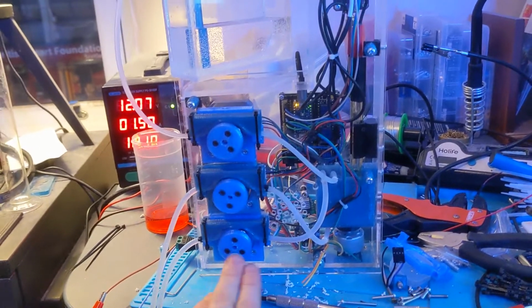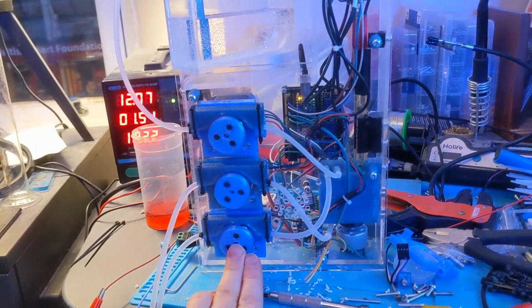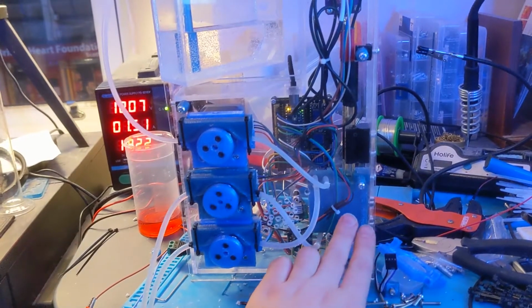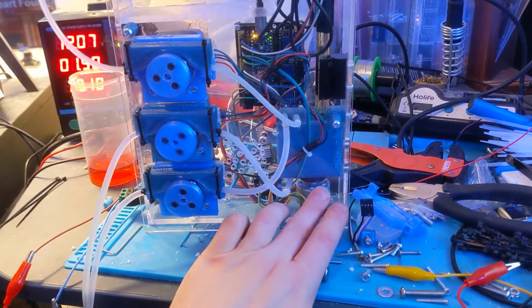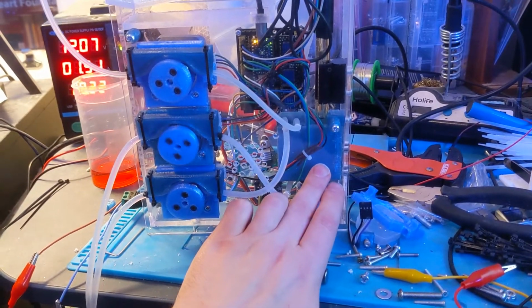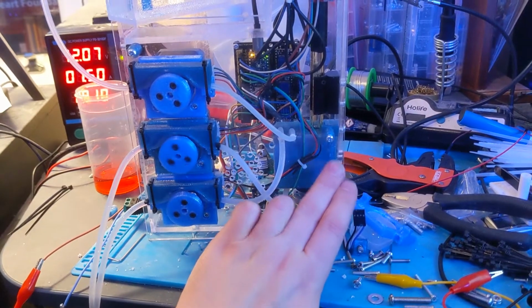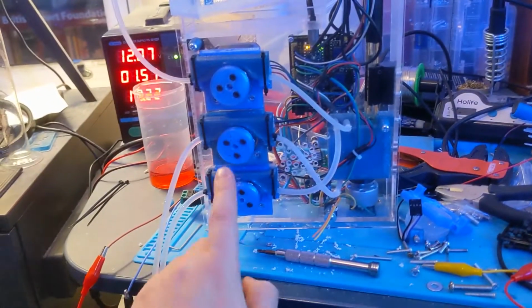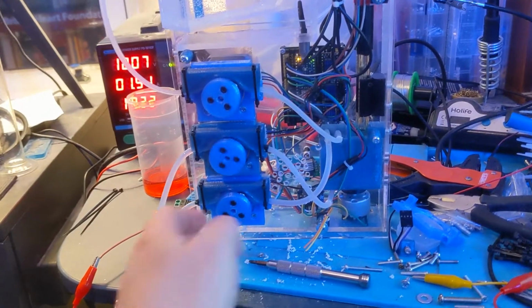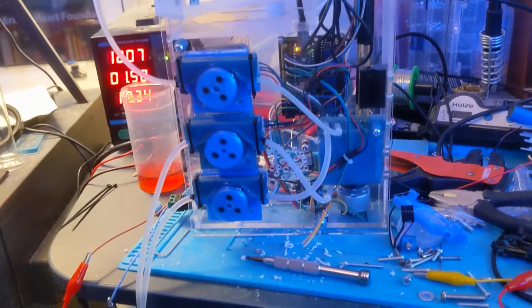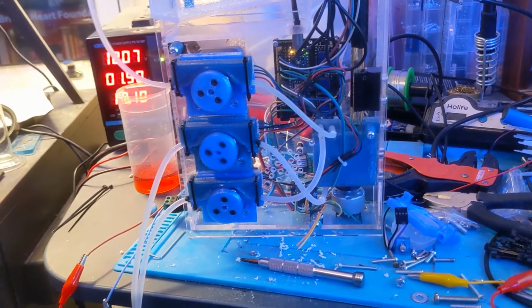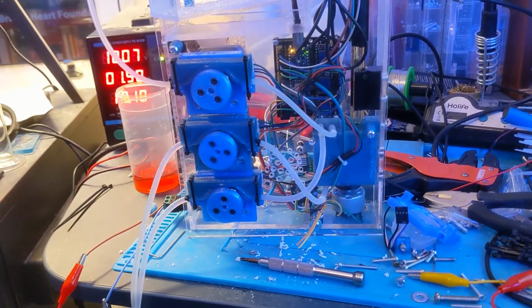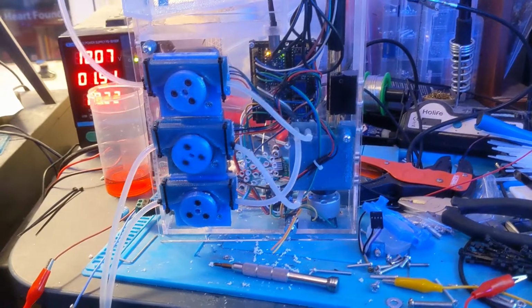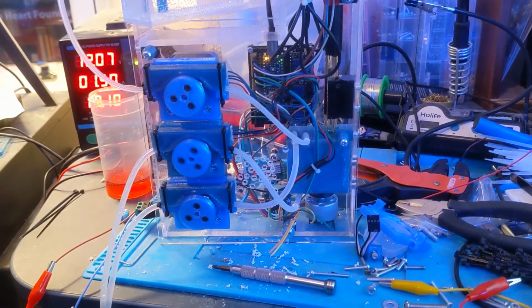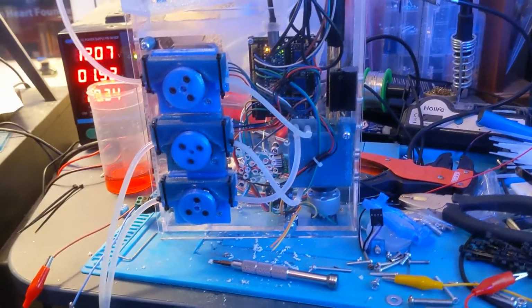Once that's finished, this pump here at the bottom, which is the tank water pump, is going to run 30 milliliters, fill that up. This magnetic stirrer motor and the magnetic stirrer bar that sits inside the chamber will spin to rinse off the inside of the chamber and the tip of this pH probe. Then the waste pump will run again to empty it, and then it will bring in a fresh load of tank water to run the test. That whole rinsing and reloading process does take, I think, 3 or 4 minutes. I'm going to set my phone down and speed up the video while that happens, and then I'll pick this up again once it's doing something interesting.